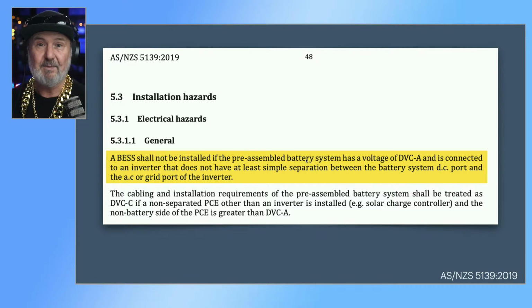I also won't say batteries, BESSes, because they include the inverter. Whereas Section 5 is where you have a separate inverter and a separate battery. And then in that case, and Section 6 as well, a BESS shall not be installed if the pre-assembled battery system has a voltage of DVCA, i.e. less than 60 volts, and is connected to an inverter that does not have at least simple separation.